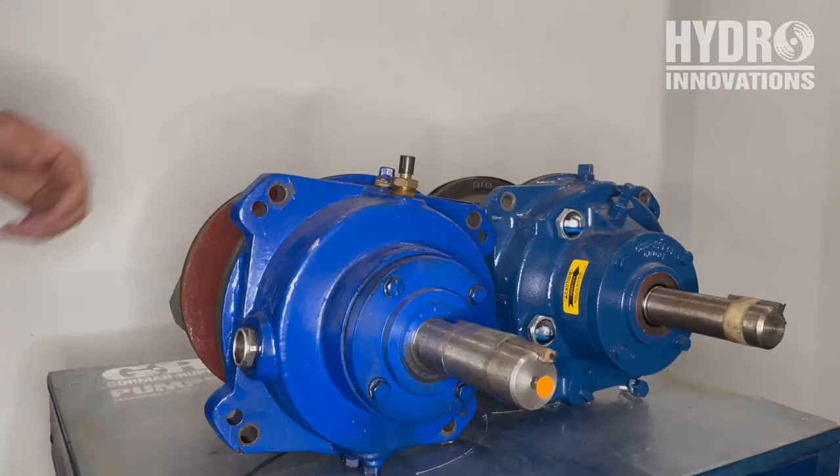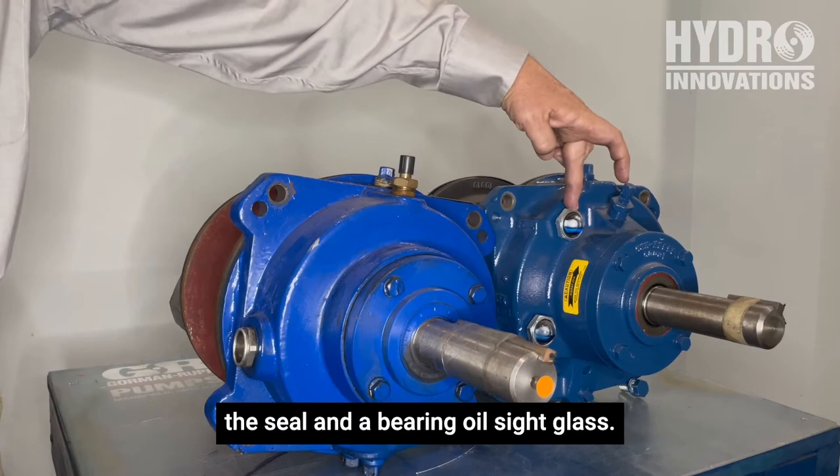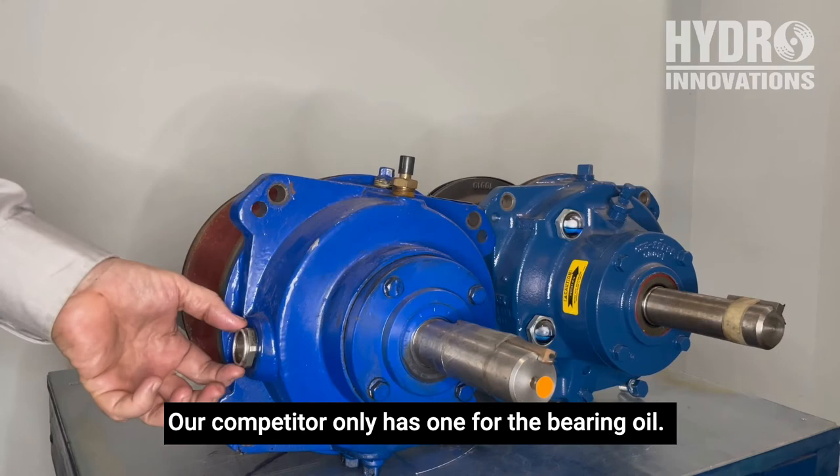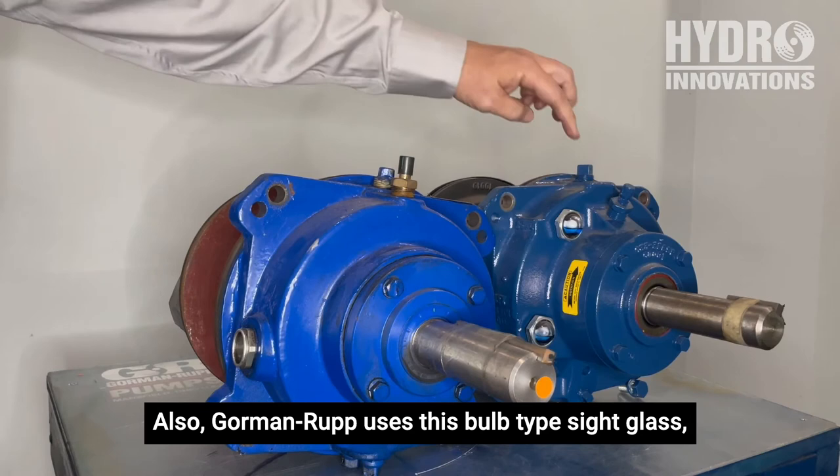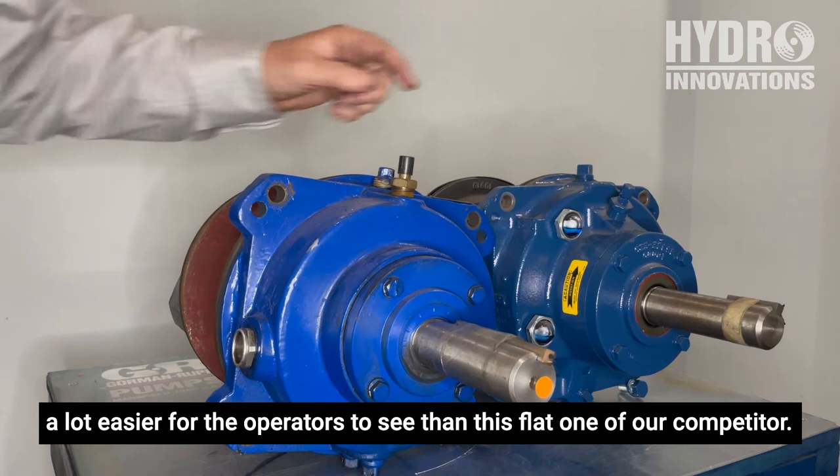The Gorman-Rupp pump is fitted with an oil sight glass for the seal and a bearing oil sight glass. Our competitor only has one for the bearing oil, and they rely on operators to remove a plug and use a dipstick to judge whether more oil is needed in the seal oil. Also, Gorman-Rupp uses a bulb-type sight glass, which is a lot easier for operators to see than the flat one on our competitor's pump.